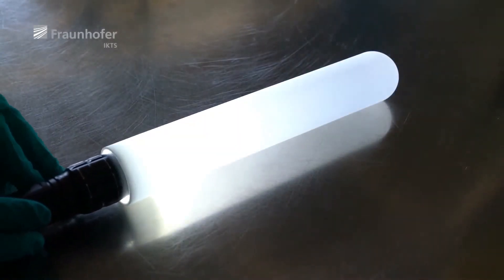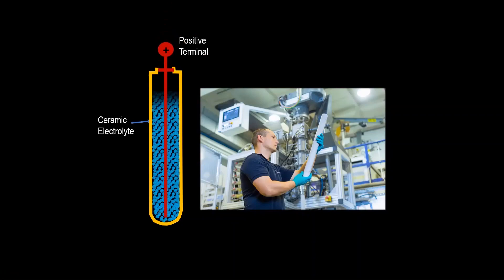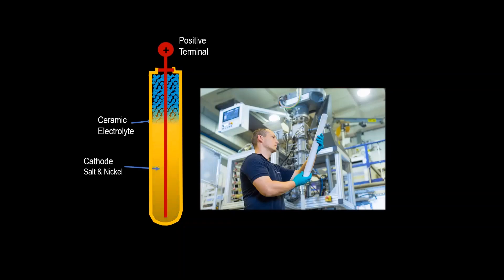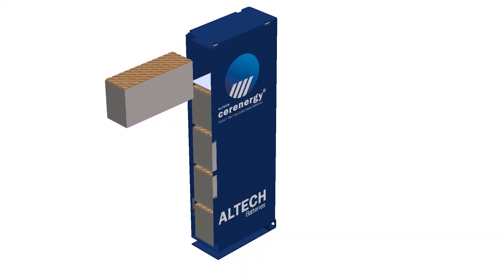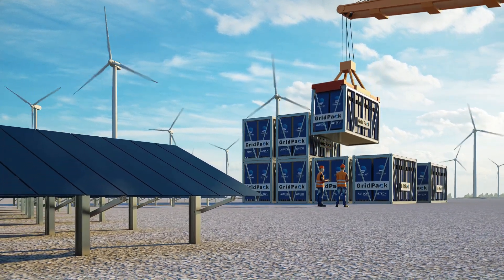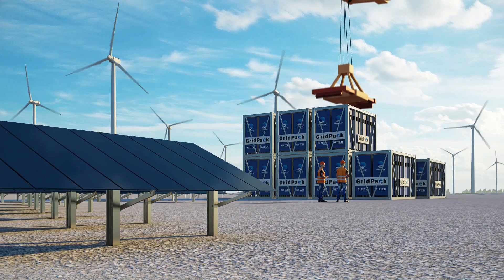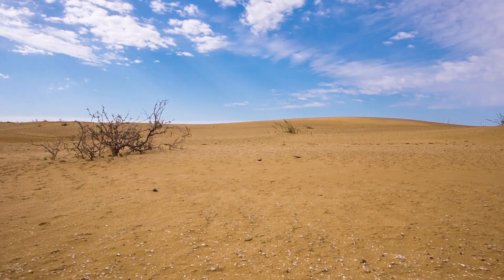The Gridpack boasts safety features and longevity. Unlike traditional lithium-ion batteries, Syrenergy's batteries do not use flammable liquid electrolytes or separators. Instead, they employ a ceramic solid-state electrolyte that makes them resistant to fire and explosion, as well as thermal runaway. One of the unique features of these batteries is that there are no moving parts, such as cooling fans like in lithium-ion battery packs. They're totally silent and can be installed close to residential neighbourhoods. These innovative batteries can even function in extreme temperatures, from frigid cold to scorching desert heat.